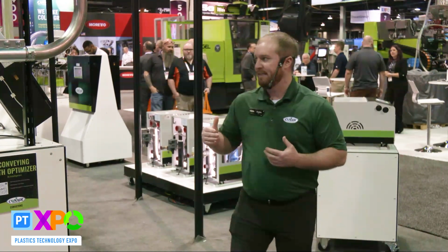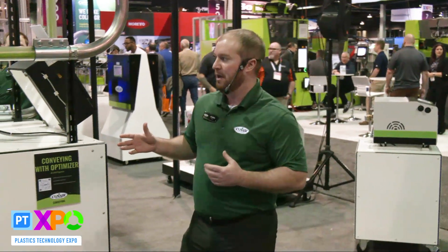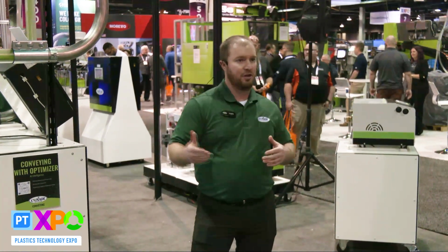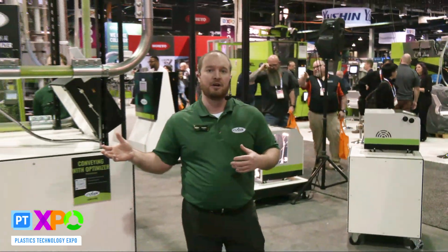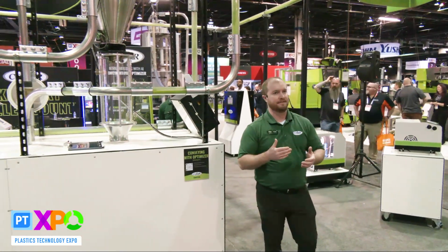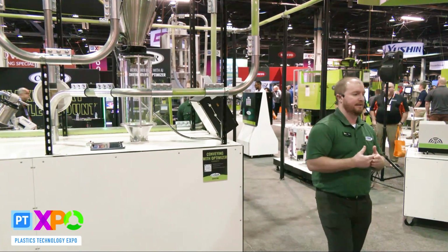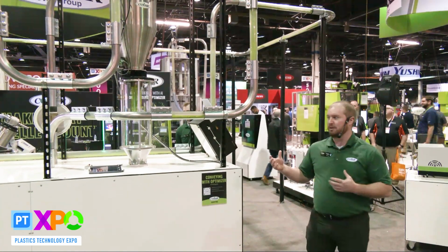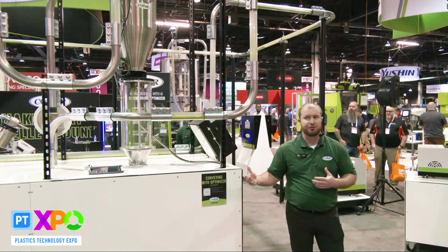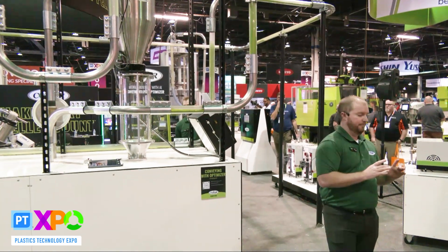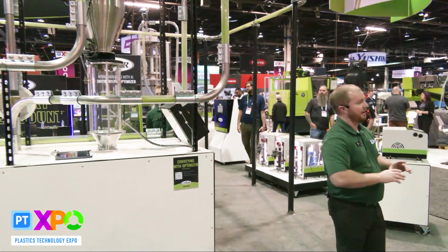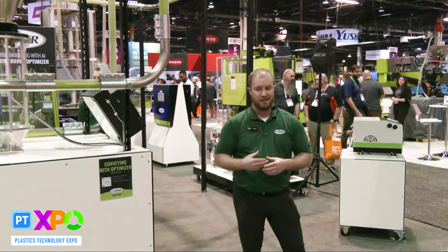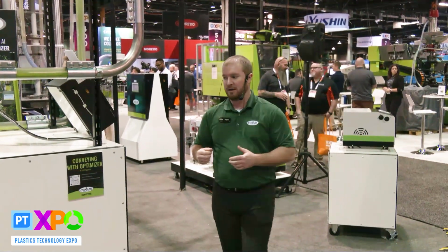With different tests that we've run in our lab, we've seen anywhere from 20 up to 40% energy savings with our ResinWorks with Optimizer because of that change in throughput, so change in airflow. Really, all that we're asking a user to do is go up to the controls that are on the drying hopper or the dryer, and all they're doing is telling us what the resin is and what the overall throughput is.